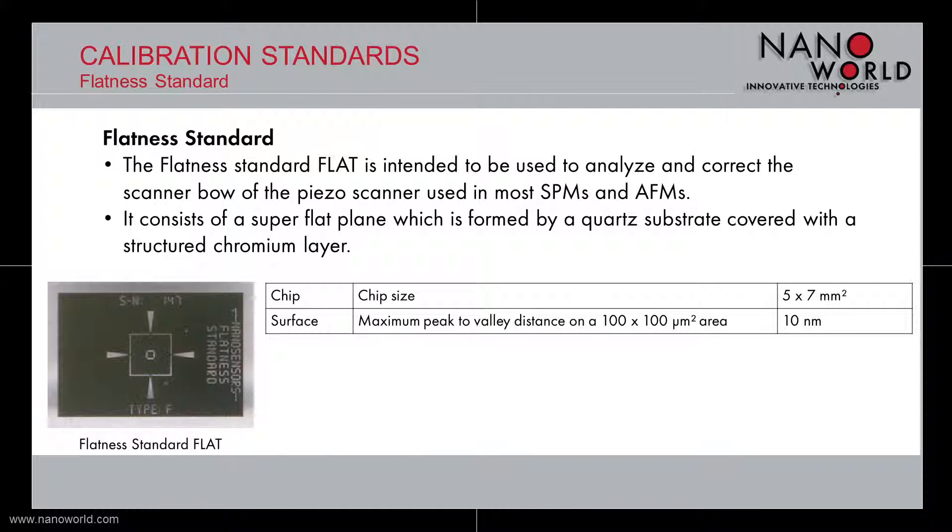The last calibration standard offered by NanoWorld is a flatness standard called FLAT. It is intended to be used to analyze and correct the scanner bow of the piezo scanner used in most SPMs and AFMs. It consists of a super-flat plane which is formed by a quartz substrate covered with a structured chromium layer.